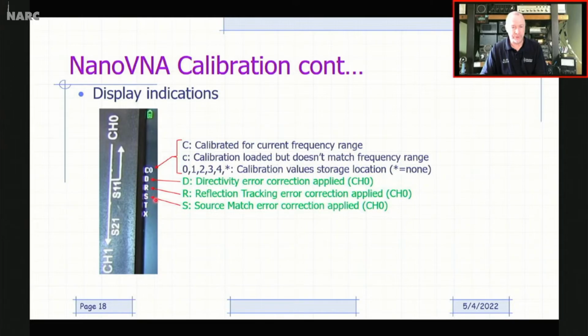Okay, the next numbers, D, R, and S, stand for the directivity, reflection, and source error corrections. We talked about those systematic errors. These are 3 of those sources of systematic errors. This is saying that we've done a calibration that's sufficient to apply the correction factors for the directivity of the coupler, in this case the measurement bridge, reflection tracking, and source matching. These again are all calibrations associated with port 1 or channel 0, the reflection port.